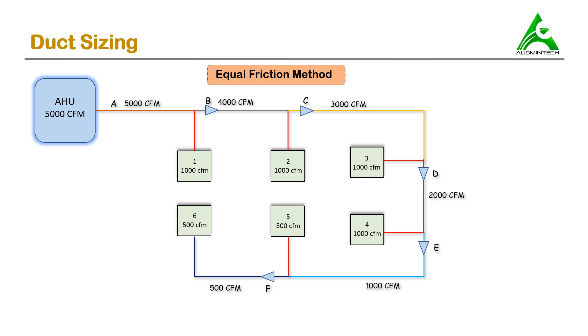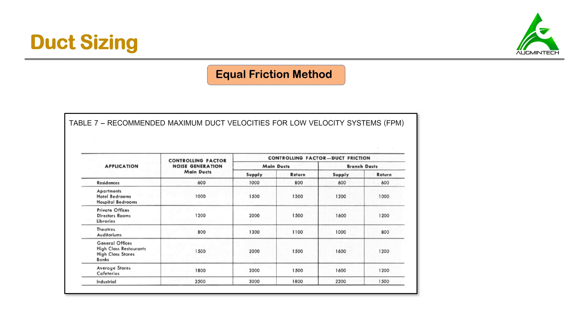We'll be designing the main duct using the equal friction method. The first step is to check that the maximum velocity of air flowing in any section does not exceed the recommended maximum velocity. As suggested by Carrier, since we are designing for a library, we look at the row for library and the column for supply duct, which intersect at 2000 FPM.